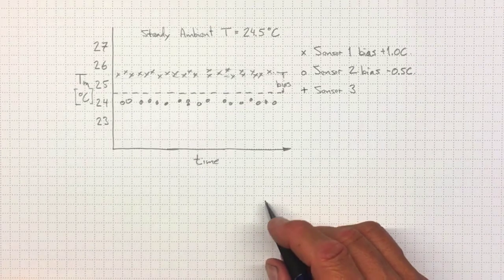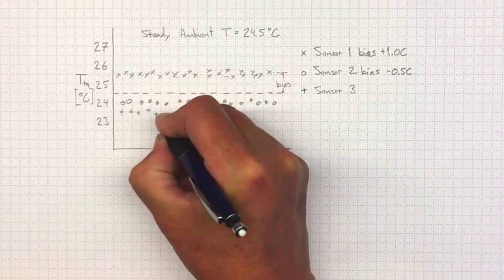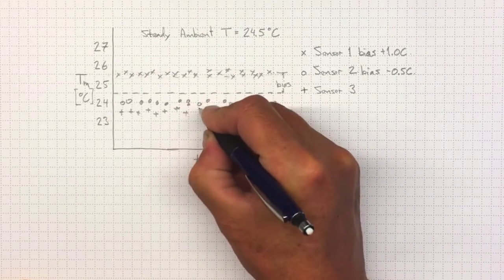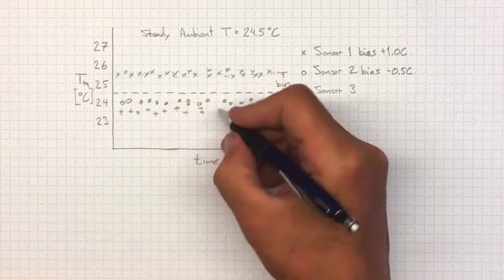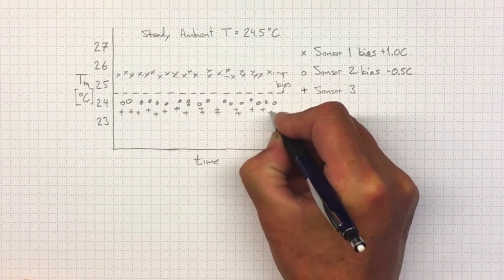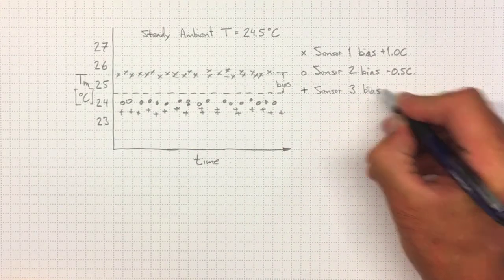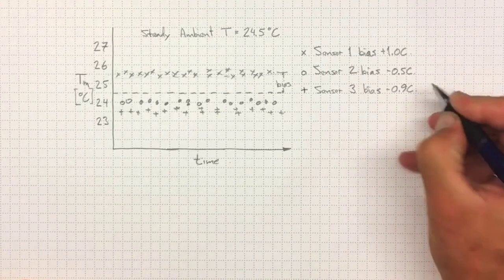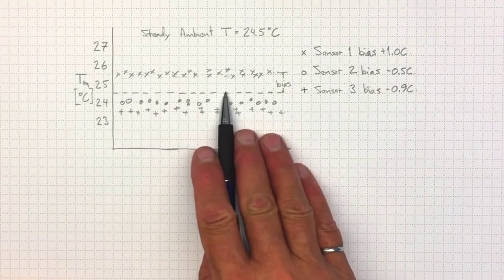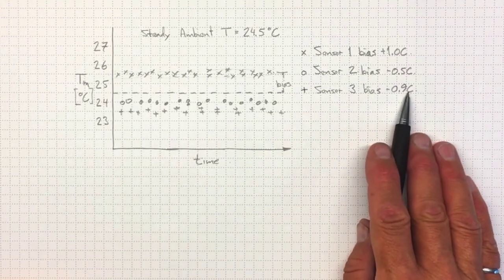Now, if I went and measured with sensor number three and I wound up down here, then sensor number three has also got a negative bias. And its negative bias might be minus 0.9 degrees C. So if I took that one and calibrated it back to the mean, I could get a pretty good estimate out of sensor number three as well.